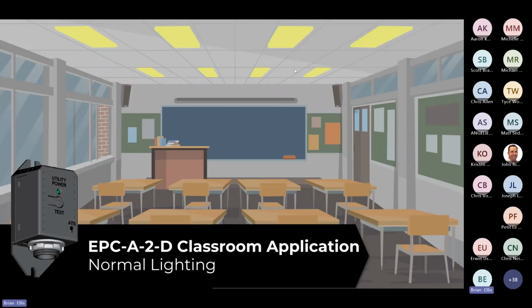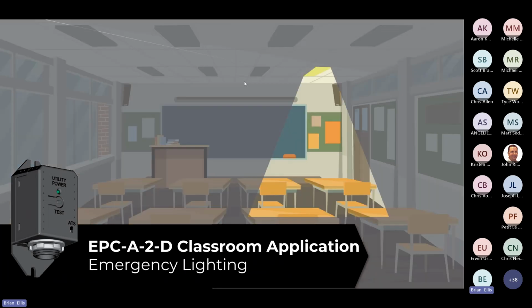Okay, here's how one of these devices works in the field. If I wire an EPC A2D to my emergency fixture in this classroom, and I have my lighting control device, whatever it is, wired to all the normal lights in this classroom, whenever power fails, the emergency light is going to go on, and the lighting control device is going to be ignored. That patented test: if utility is present and all these lights are on, but I walk out of the room and flip the switch off, the normal lights go off automatically and the emergency light will stay on for an additional 2.5 seconds. So there's a 2.5 second delay off with that patented audio or visual test.